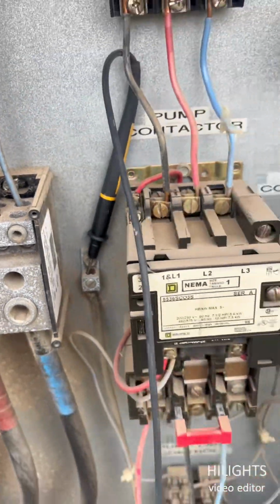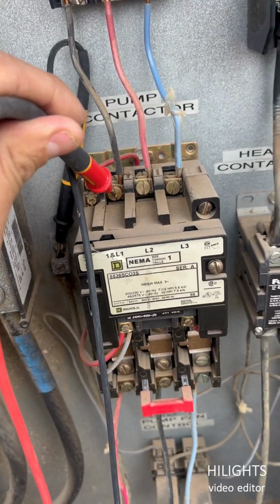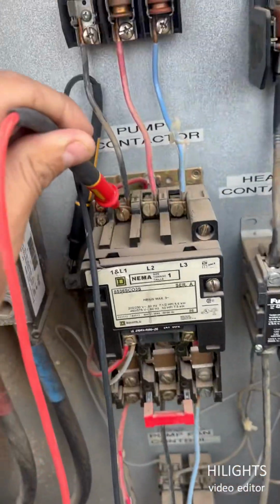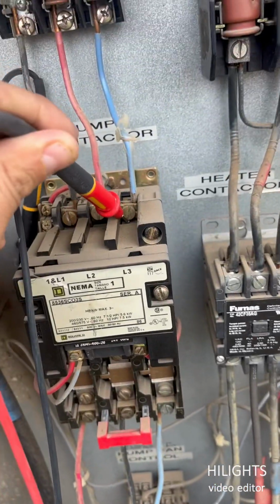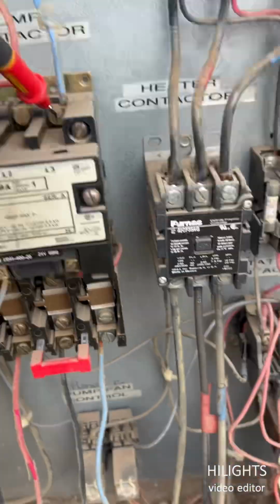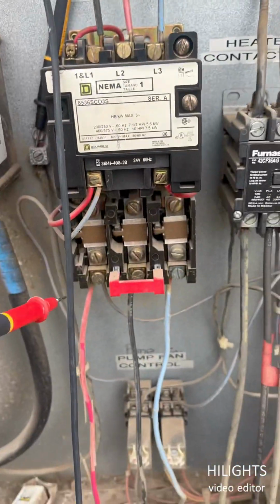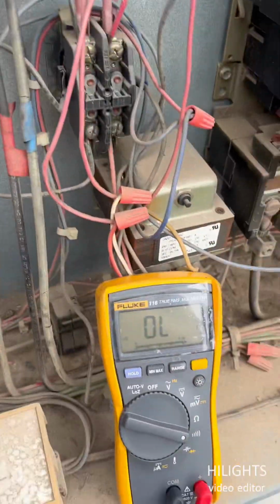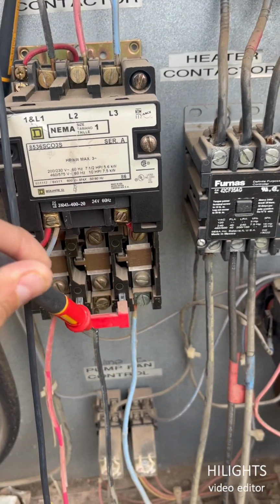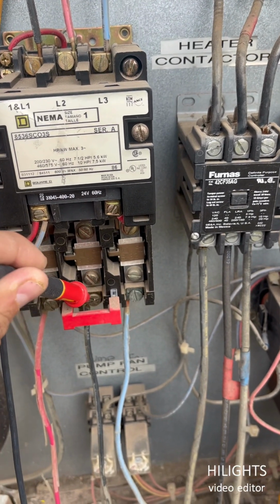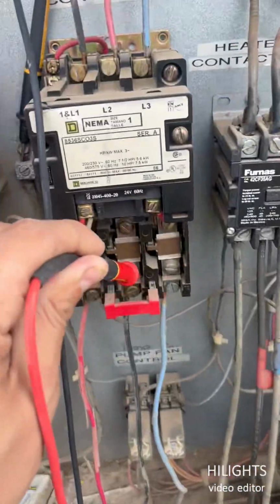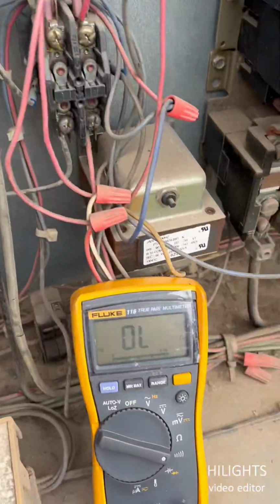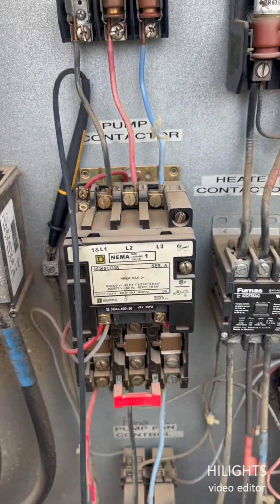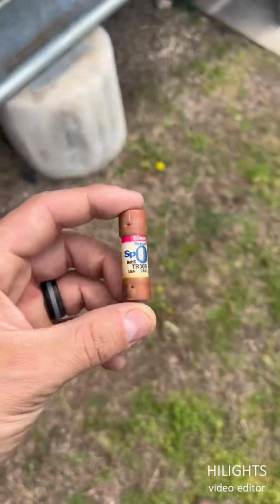Alright, now I'm going to check the contactor to ground also, because I have had some contactors that were actually bad, and those tripped the fuse or tripped the breaker. So we're checking each terminal on the contactor for the high voltage, making sure it's not shorted to ground, which is reading open, so that's good to ground. Alright, contactor's good. Bad fuse, let's go get one.